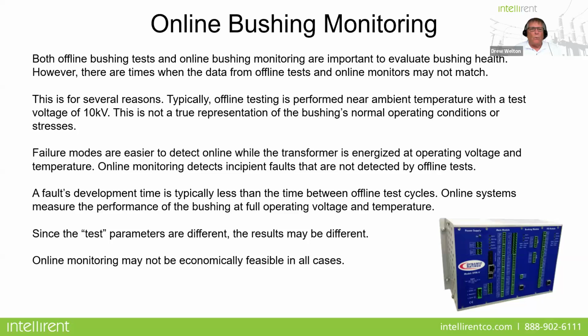Now, one final word about online bushing monitoring, and my friend Brian, I'm sure, will tell you all about this. What's really nice about online monitoring is that it gives you a consistent evaluation of the bushing health. You will see times where the bushing monitoring gives you different results than doing it offline. Why is that? You're under normal operating conditions at normal temperatures, and this makes failure modes a bit easier to detect online while the transformer is energized at operating voltage.